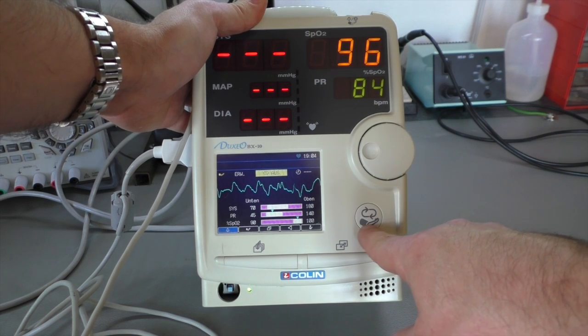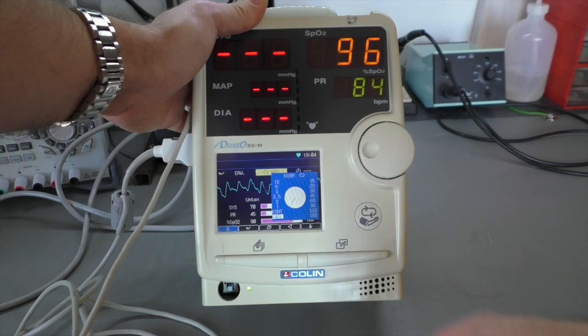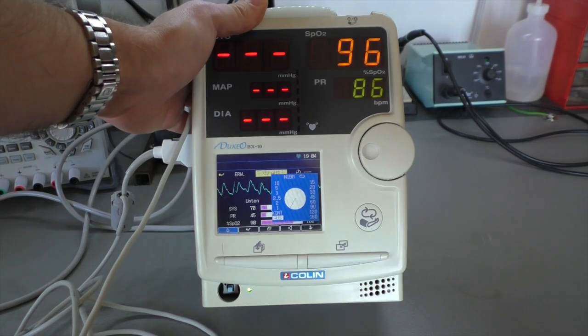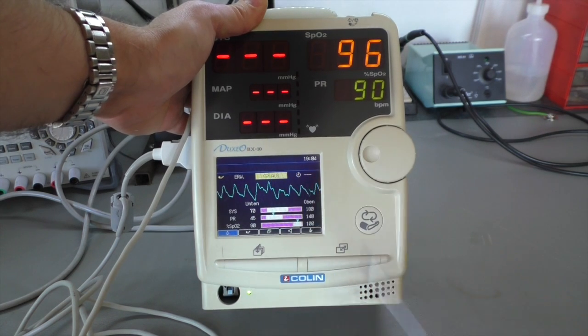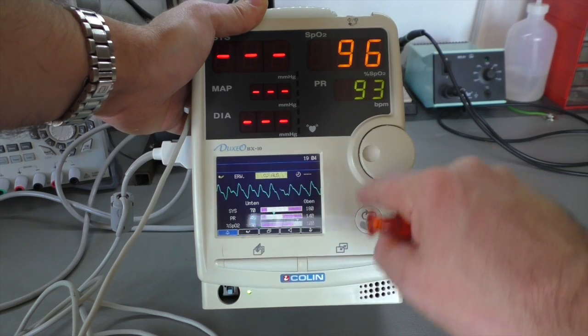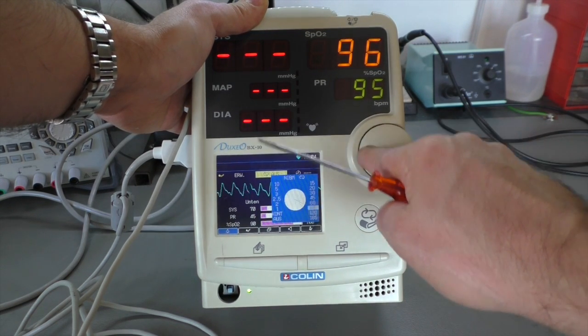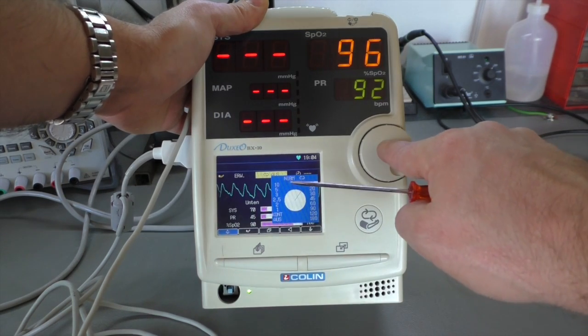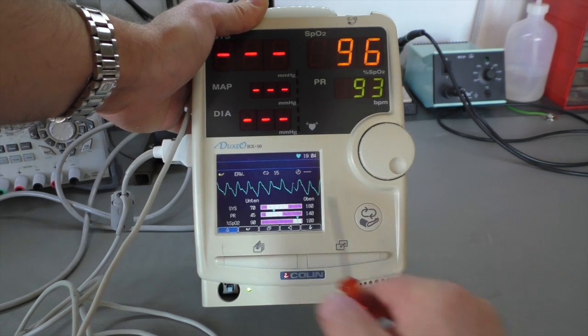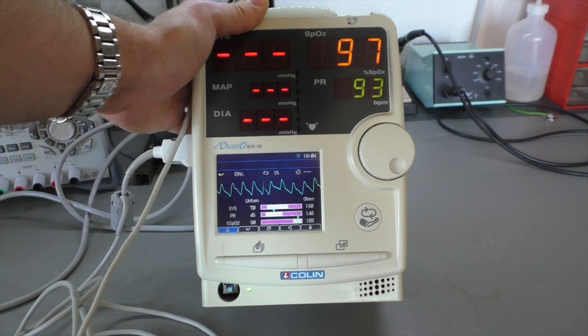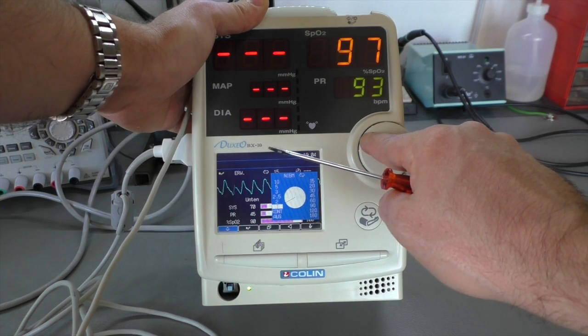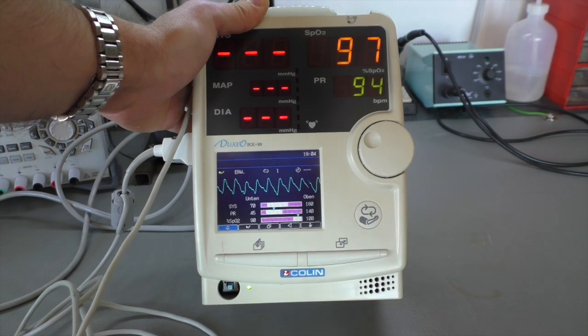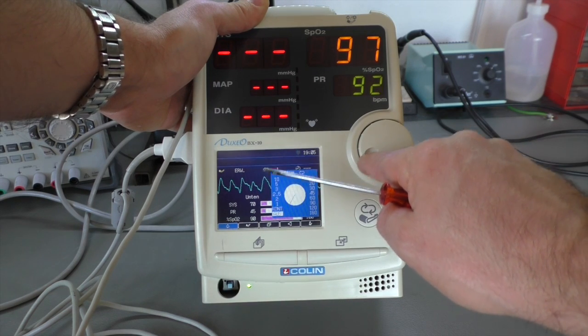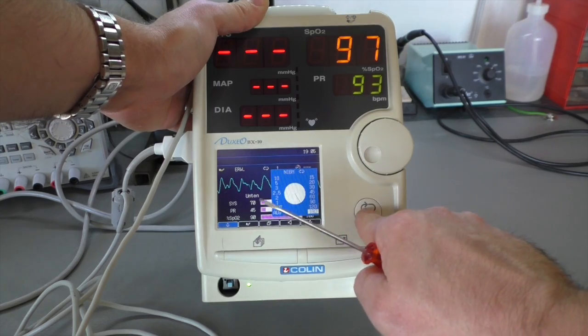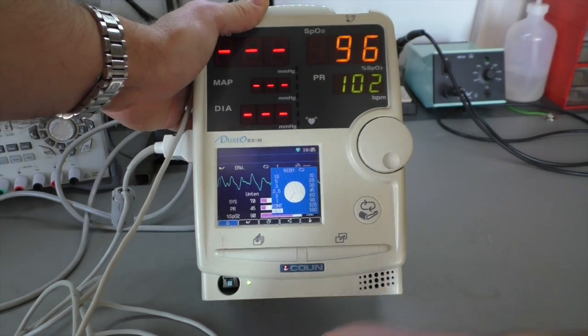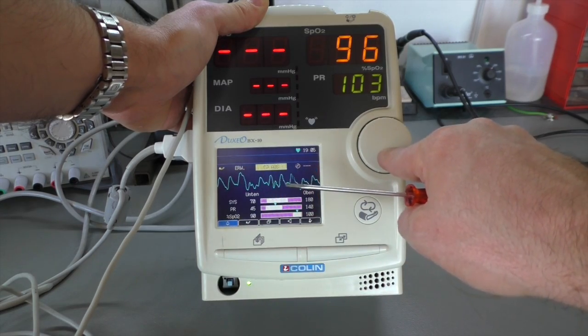Here is the symbol for the blood pressure measurement. If I press this, it's now on "aus", that means off. So we don't do any measurement because I don't have the equipment to do that. We can select here the time in minutes. So for example, we want to make a blood pressure measurement every 15 minutes. So I set that. You can see it here, cycle 15 minutes. 1 minute. I could measure the blood pressure every minute, but I think patients won't like that because, well, it's always this pumping of this cuff around your arm. So I set it off.